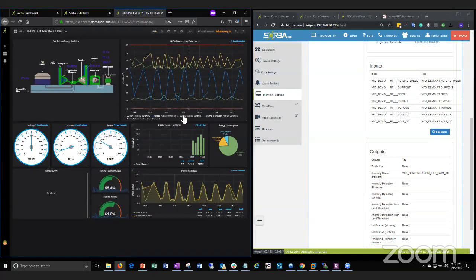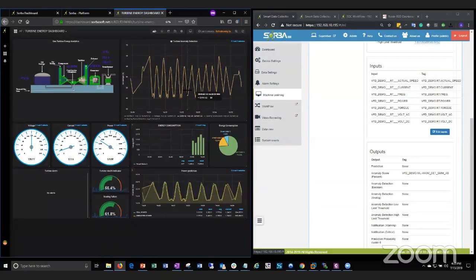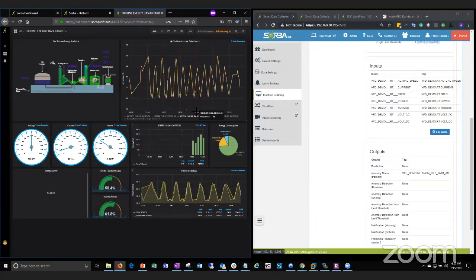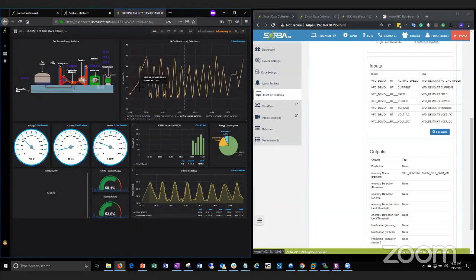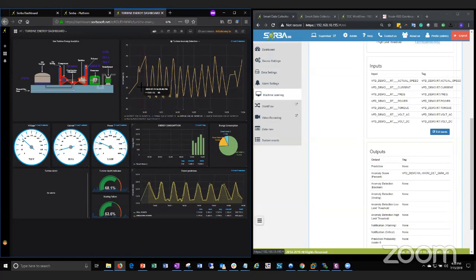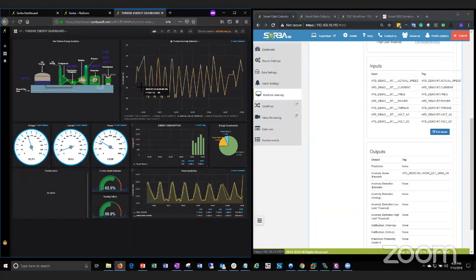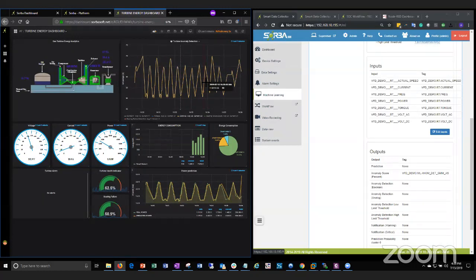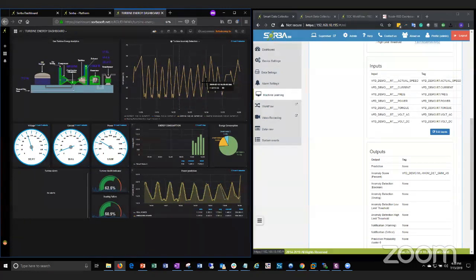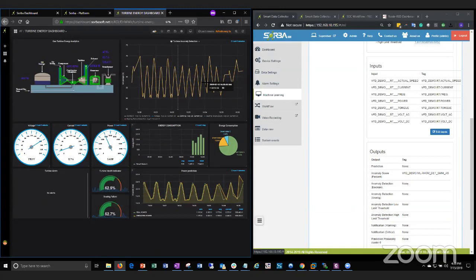Here I'm predicting an anomaly, which is the output of this particular algorithm. This big sine wave is sending me a value between 0 and 100%, deciding between current, temperature, voltage, torque, and so on what is an abnormal condition. If this anomaly detection goes above 80%, that's the threshold when we send an alert telling us there's an abnormal condition. Because the VFD is constantly moving back and forth, I've got this in a repetitive ramp up and down mode.